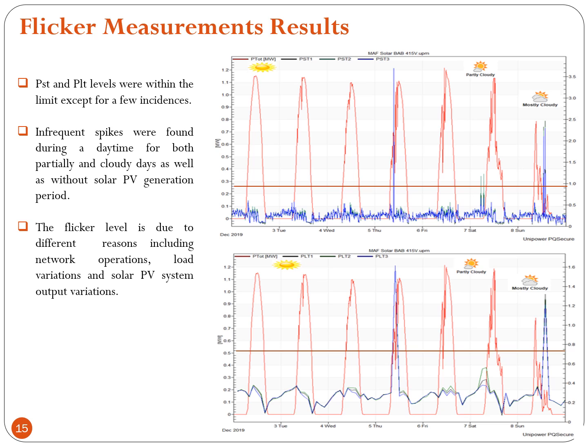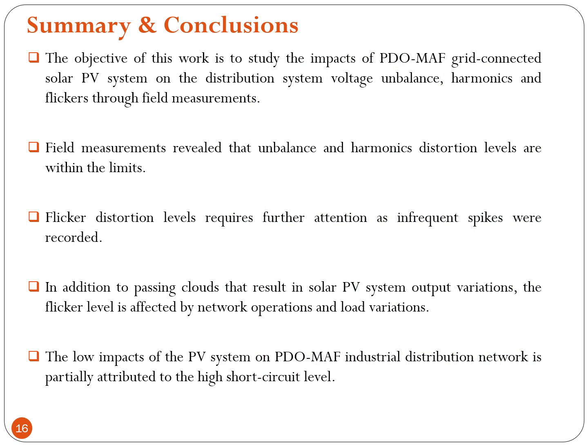Flicker measurement results show that PST and PLT levels were within the limit except for a few incidences. Infrequent spikes were found during the daytime for both partially cloudy and cloudy days, as well as during periods without solar PV generation. The flicker level is due to different reasons, including network operation, load variation, and solar PV system output variations. Finally, summary and conclusion.